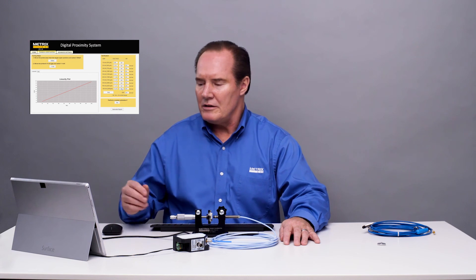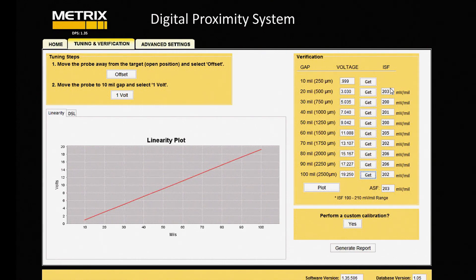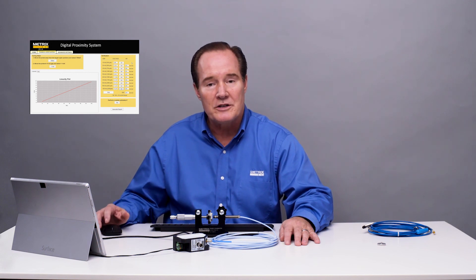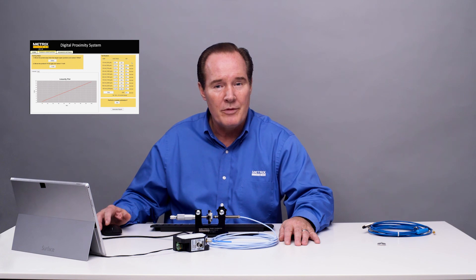All right, that was our last point. And if you look at the incremental scale factor, it's between 190 and 210 millivolts per mil. That's really excellent for our proximity probe system. And it shows that the Metrix Digital Proximity System works with a competitive probe and cable. Thank you very much.